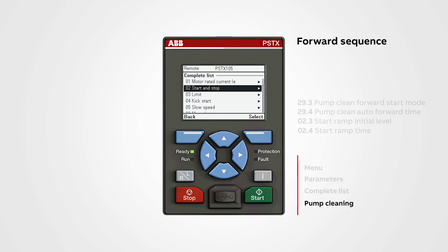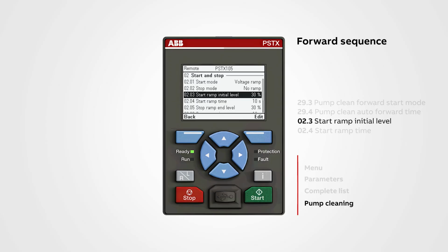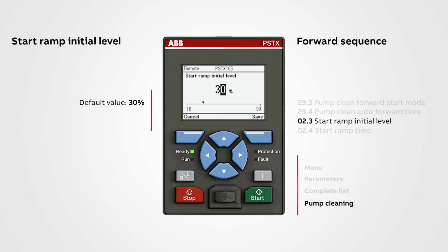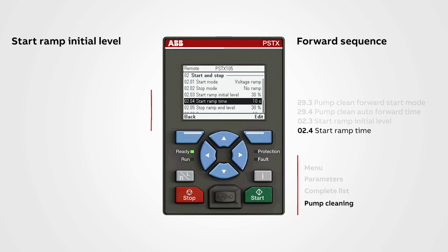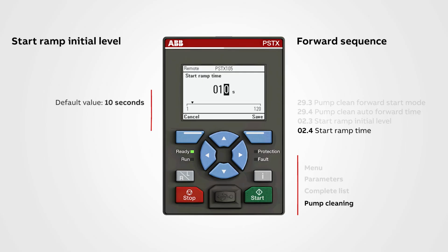Now let us look at the alternative parameters that are important to set if you did not select the full voltage ramp. Parameter 02.3, start ramp initial level. This will set the level the ramp should start ramping from. The default value is 30%. The range of the setting is between 10 to 99%. A low value can result in the motor stalling in the first part of the ramp, and too high a value will result in a jerk when the ramp starts. And if we look at parameter 02.4, start ramp time. This parameter will determine how long it will take to ramp the voltage or the torque from 0 to 100% voltage. The default value is 10 seconds. The range of the setting is between 1 to 120 seconds.